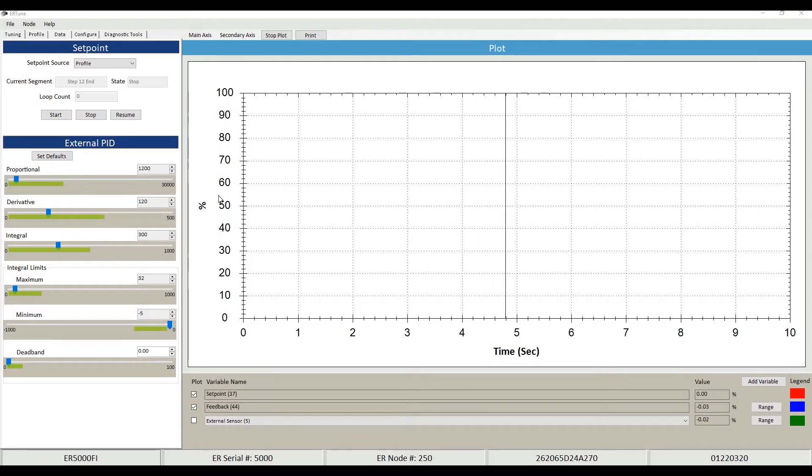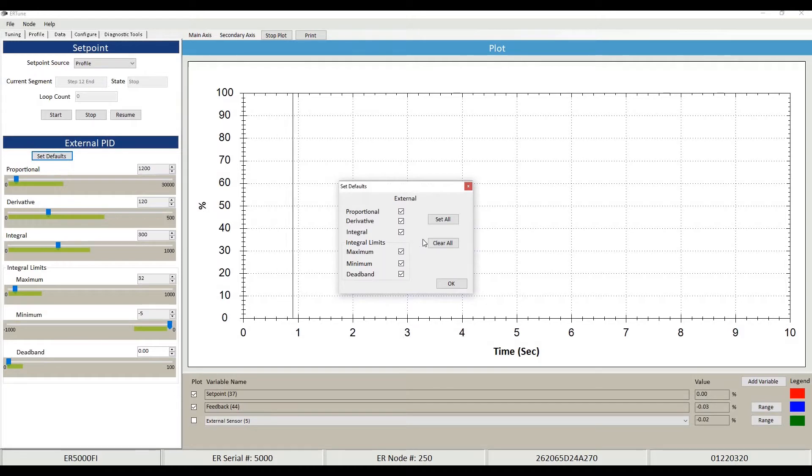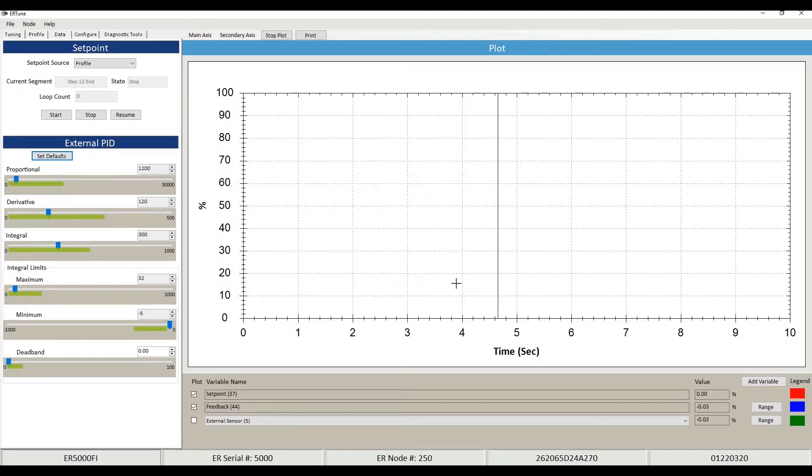Here we are in the interface of our ER Tune software. What I've got here is our basic interface showing our PID controls, which allows you to change your proportional, derivative, and integral modes to give tighter tuning on things like changing set points and keeping certain pressure active for a certain amount of time. I've set the defaults here — it does come with its own defaults and they're pretty tight, giving about a second to a second and a half on pressure changes.